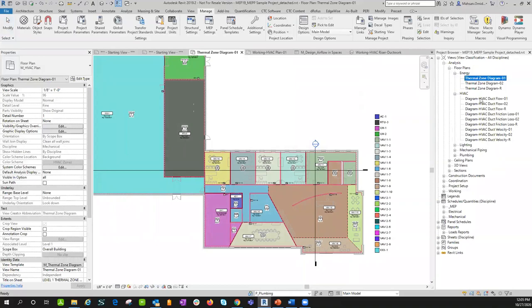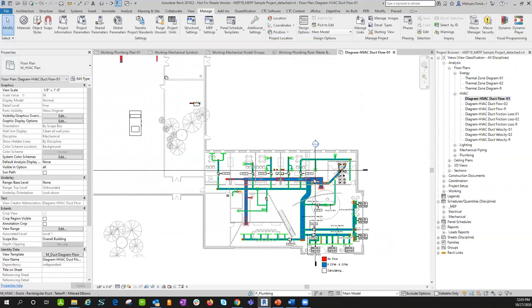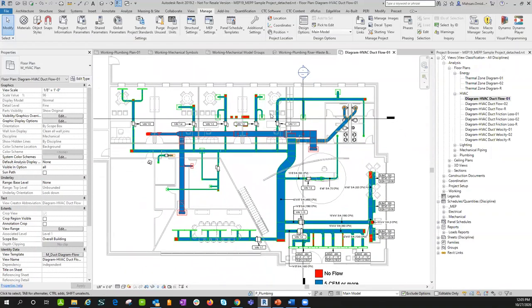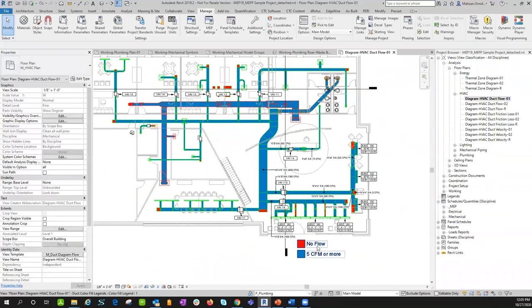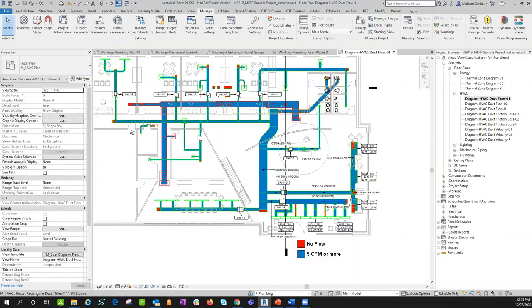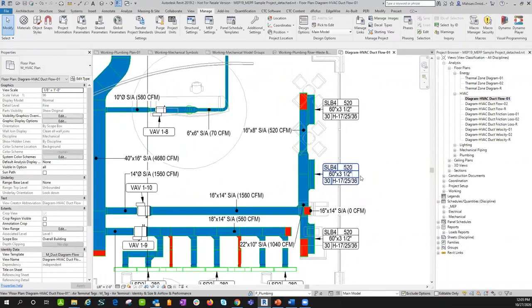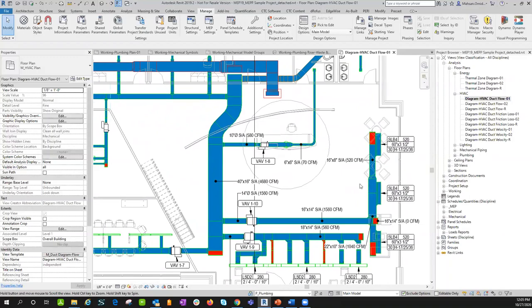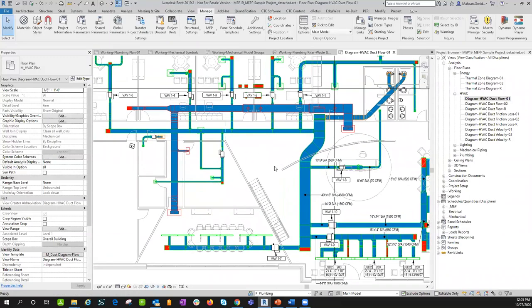Each view is created by the right view template that CTC has set up. If I go into the identity data and view template of my thermal zone diagram, you will see that the color scheme HVAC zones are assigned into that color scheme. In your HVAC design diagram, for example, you'll have a different kind of color scheme based on the velocity and flow going on inside of your ducts. Those red markers show that there is no flow inside of them, but as soon as you select any of those ducts, the supply air flow CFM is going to be color-coded so you know at any time which diffuser is connected and which ones have a flow currently calculated.